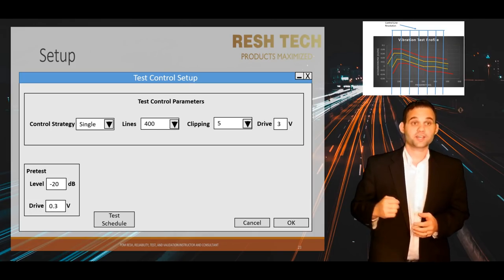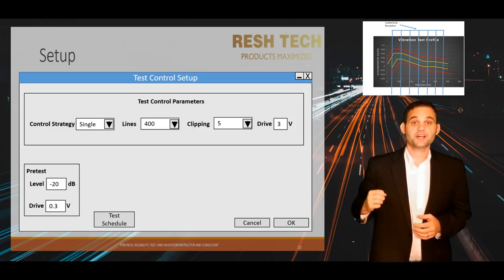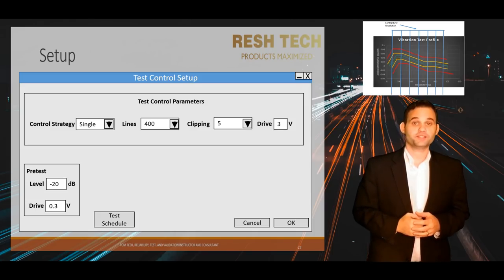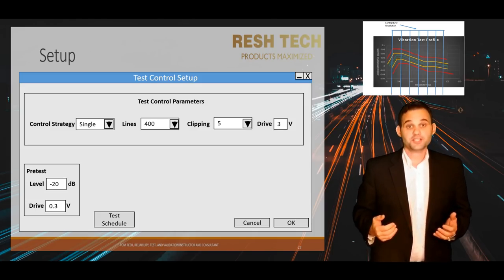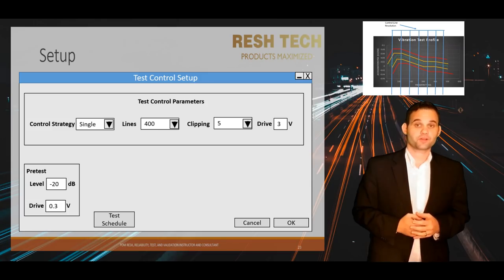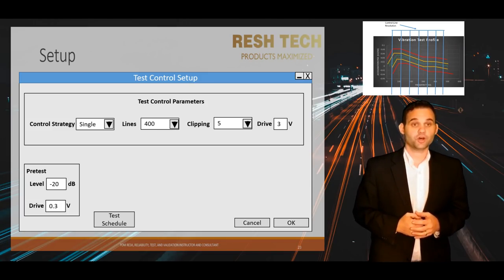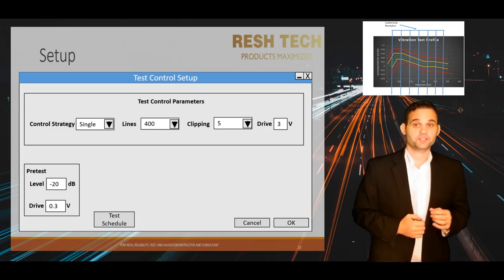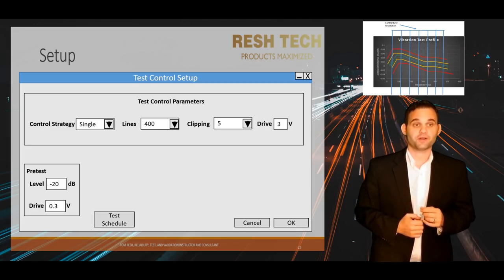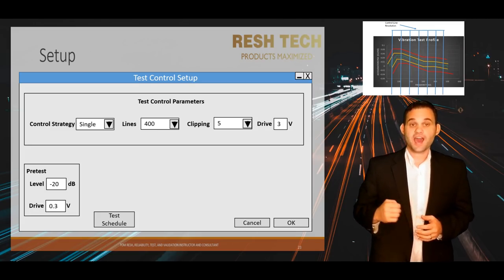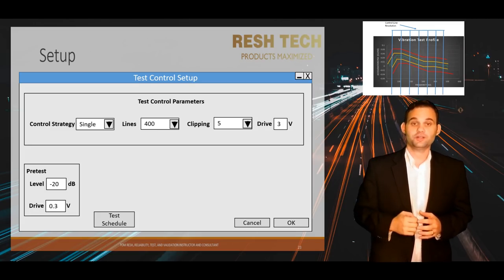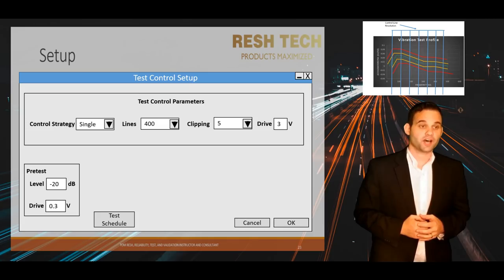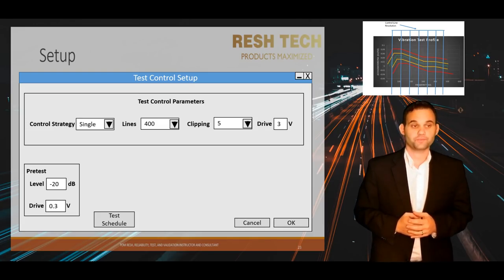Likewise, the lower the control number, the fewer points or frequency bands are used for control. This speeds up your control response time, but setting this value too low may cause your drive output to not follow your test profile adequately, and could lead to an out-of-tolerance or even abort limit issue.